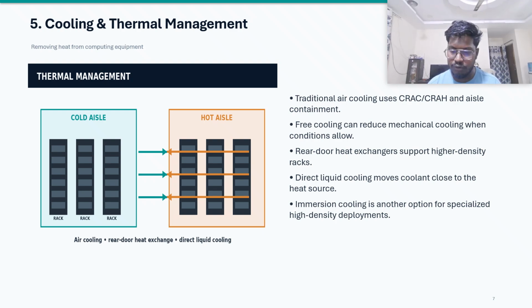So instead, we are using a liquid cooling system, where the liquid is a non-conductive water, as I mentioned. If we put it on a server or processor running 24/7, it works just like water - liquid can transfer heat much more efficiently than air.